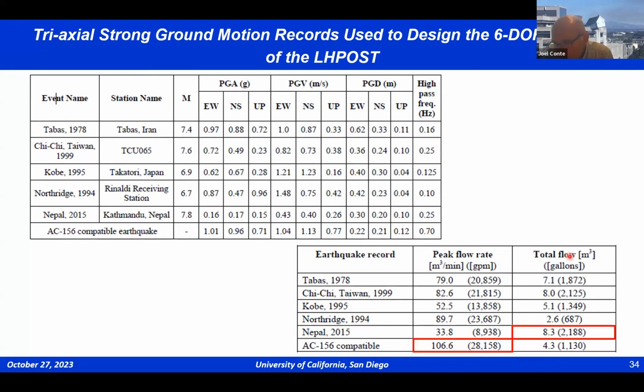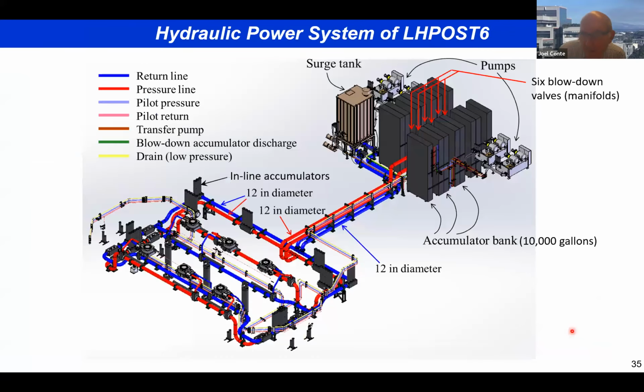And then in terms of total flow, 2,200 gallons. Right? And this should represent only about 20 to 25% of the accumulator bank. So that's why we chose an accumulator bank of 10,000 gallons. So we had to multiply our accumulator bank by a factor of 2. So now 10,000 gallons. And now we have 6 blowdown valves instead of 2, and we bought 2 more pumps.